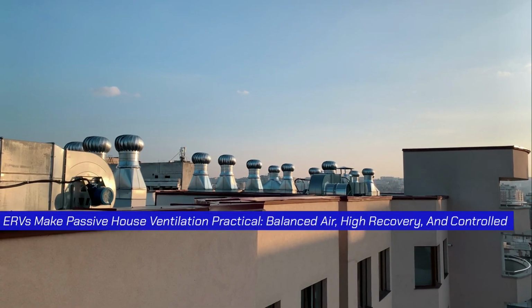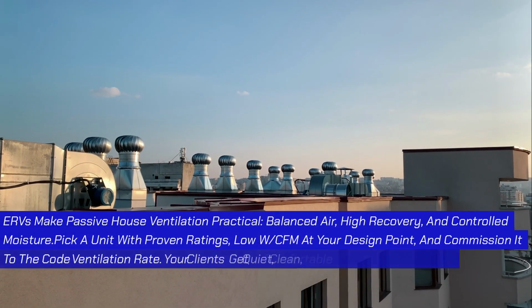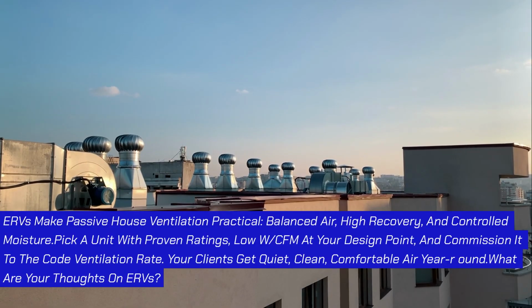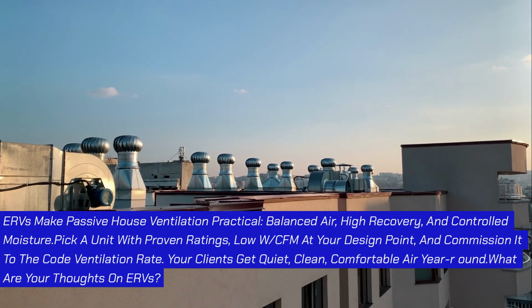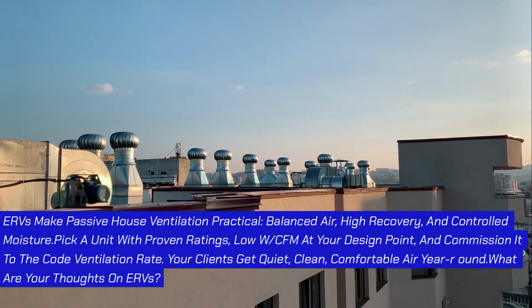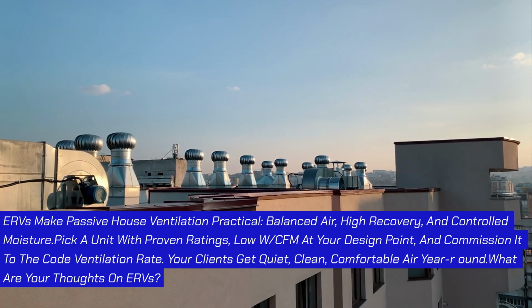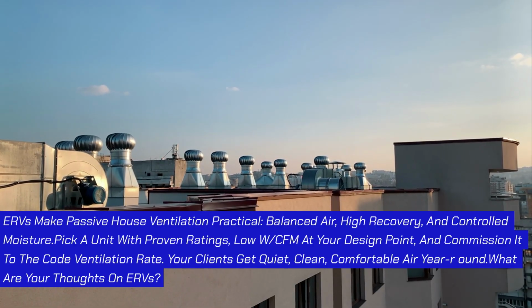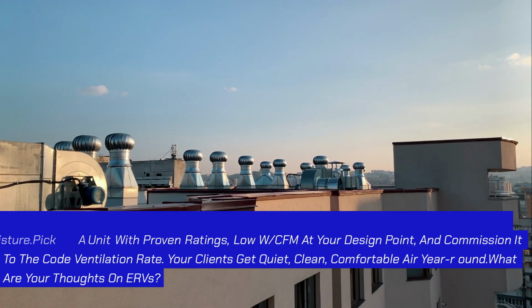Conclusion: ERVs make passive house ventilation practical. Balanced air, high recovery, and controlled moisture. Pick a unit with proven ratings, low W/CFM at your design point, and commission it to the code ventilation rate. Your clients get quiet, clean, comfortable air year-round.